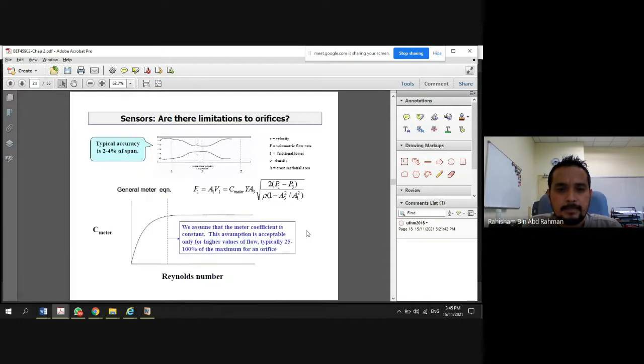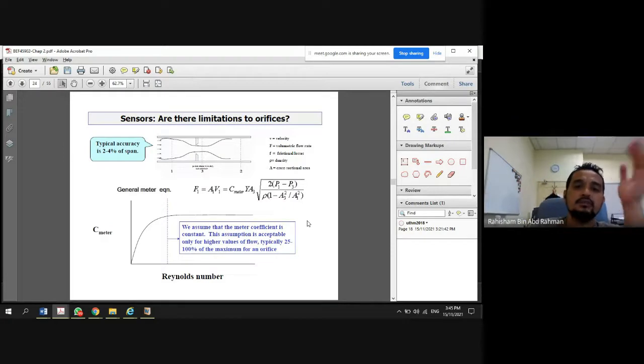Okay, all right, sensor. Are there limitations to the orifice? We use the orifice plate. Typical accuracy is 2 to 4% of span, which is relatively acceptable, not really a big one.